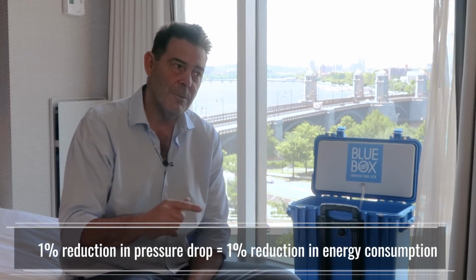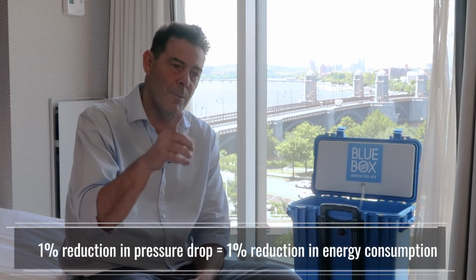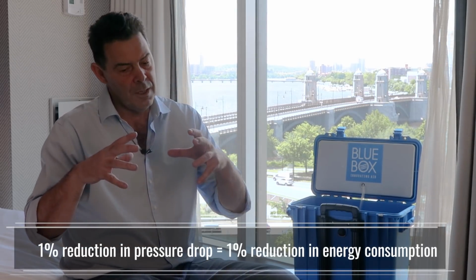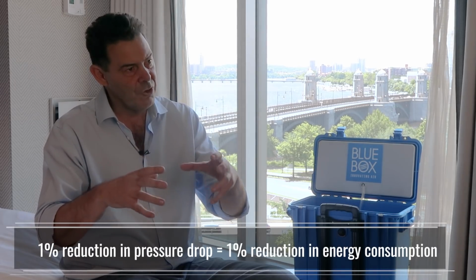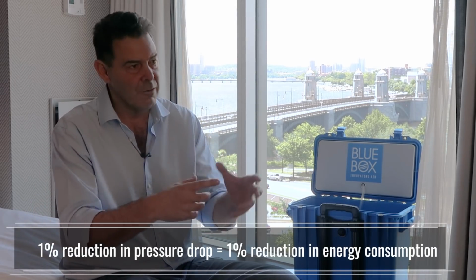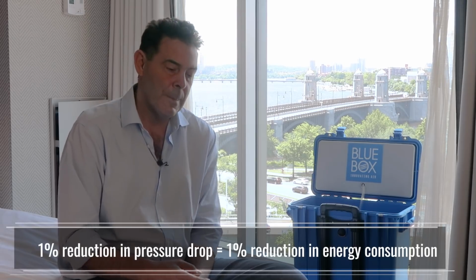The rule of thumb in HVAC is a 1% reduction in pressure drop typically equates to a 1% reduction in the energy consumption of the motor, or technically the brake horsepower of that motor. So they took their measurements, and I delivered a pressure drop, or reduced the pressure, by 40%. Wow, so the motor's working 40% less hard.